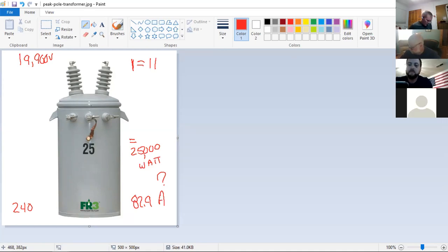Is it 912? And your math was 11 times 82.9, correct? Yes, sir. All right, and your answer was? 912. 912 amps. That's the same reading you should get down here on your bushings for the transformer and the secondary lines. Excellent. Combined, right? Combined, yes.